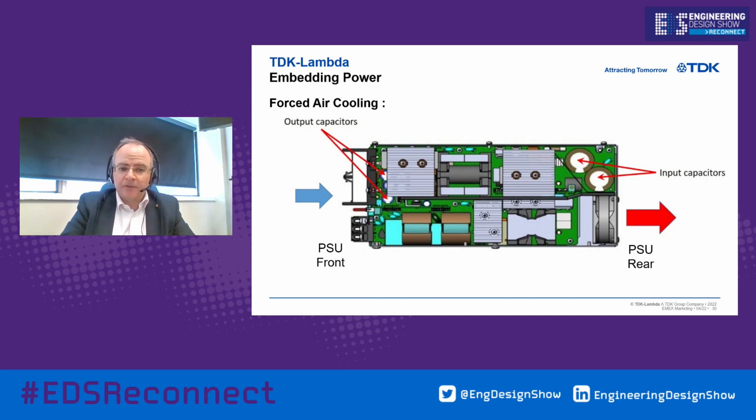The higher speed airflow cannot easily be directed at hot items like magnetics, so this is also a disadvantage. Hot air is also drawn across the fan bearings, which could affect fan life. The higher the temperature, the faster the bearings will wear due to loss of lubricant. If the fan speed is controlled according to ambient temperature, then this could also be mitigated. Also, for this reverse airflow, derating is likely to apply.